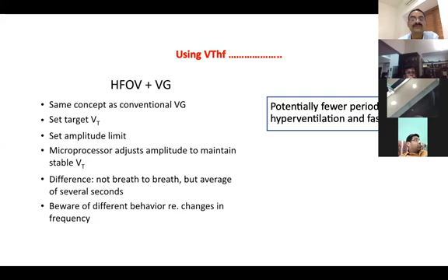But you should remember, there is a difference here. The machine does not calculate breath by breath, because each breath is of small duration. What it does is, it will calculate based on a few seconds, 3 seconds of the tidal volume, it will average. So that is how it will calculate, and the microprocessor in the next 3 seconds will adjust. So there is a latent period. You should remember this. It will come handy when you actually put a baby on HFOV-VG. And of course, when you change, do not touch the frequency. If you change the frequency, the equations will reverse depending on whether you have reached the tidal volume or not. I'll come to this. But the summary is that actually you will have fewer episodes of hyperventilation and hypoventilation. So you'll be able to wean the baby fast.